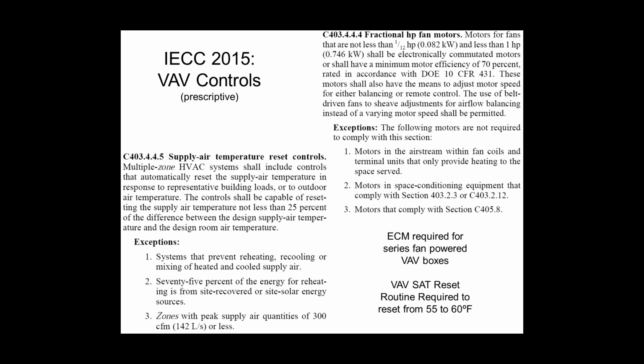But if you have multiple zone VAV systems, or VVT systems for that matter, you cannot provide a constant discharge air temperature. You need to reset that from 55 to 60 degrees, or some version of that. There's an exception there for systems that prevent reheating, recooling, or mixing of heated and cooled supply air. If you have a hot water coil, if you have an electric heater, if you have a fan-powered box, anywhere on your VAV system, even if it's just one zone, you can't use that exception. If you had a 100% cooling-only system and there's no possible source of heat at any of the zones, then that would be fine. You wouldn't have to do this reset because obviously you're in a place that needs cooling all the time. You're in some very hot place like Qatar or something like that.